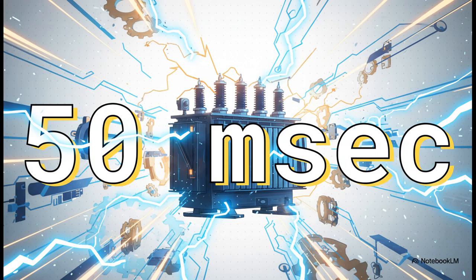When a severe short-circuit fault hits, that MCCB muscle has to trip instantaneously. And the spec doesn't leave instantaneously up to interpretation, it strictly defines it as under 50 milliseconds. That lightning-fast reaction time is exactly what stands between a healthy transformer and catastrophic, irreversible damage.